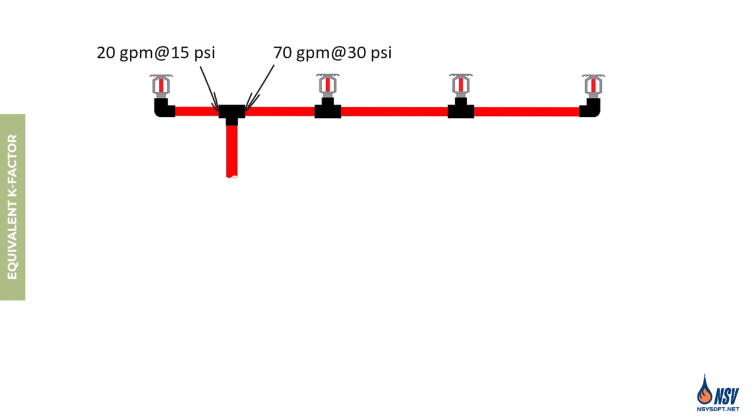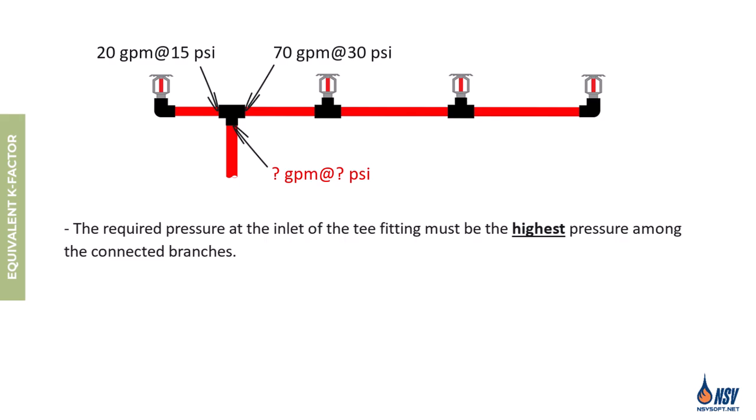Likewise, a flow rate of 20 gpm at 15 psi is calculated at the left outlet of the tee, which supplies the single sprinkler. With these calculated flow rates we can be confident that each sprinkler meets the minimum density required by NFPA 13. The question is what flow rate and pressure are required at the inlet of the tee to supply all four sprinklers. Note that we'll ignore minor losses in the tee fitting to keep this section straightforward. Where the outlets of a tee require different flow rates and pressures, the required pressure at the inlet should match the higher of the two outlet pressures — in this case, 30 psi.